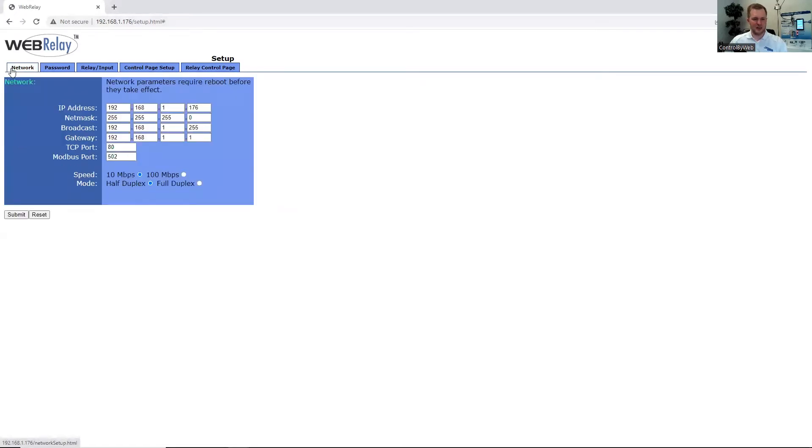Under the Networks tab we can come in and configure the network settings to our local network. By default, the TCP port and Modbus port are defaulted to these port numbers. You can change those ports to fit best for your application needs. Speed is defaulted to 10 megabits, which is recommended as it will use less power and increase the life of the unit. Mode is defaulted to half duplex, which indicates how the unit is communicating data over the ethernet connection.